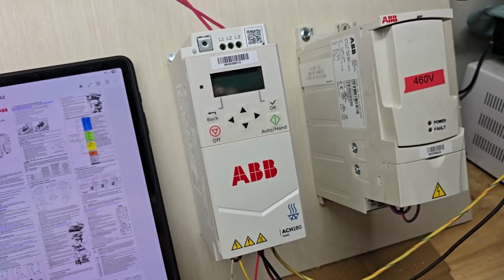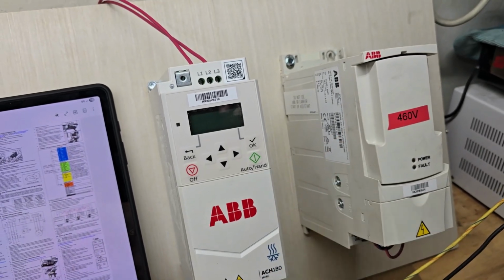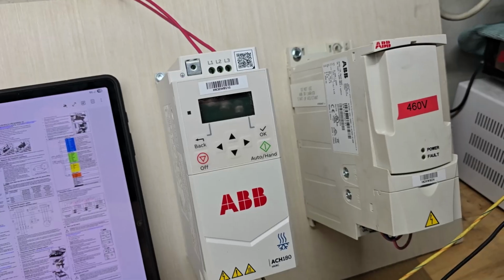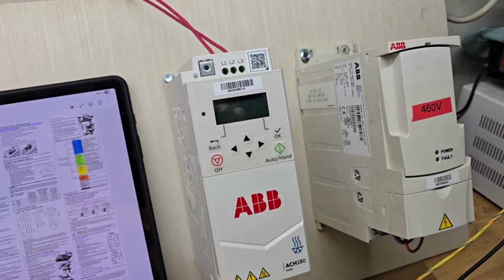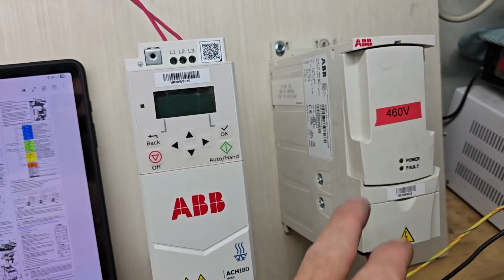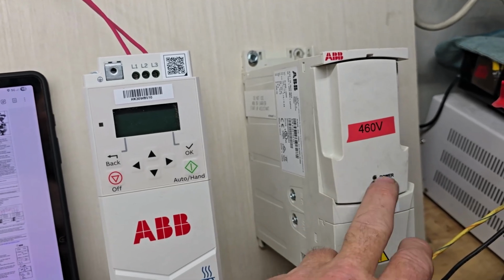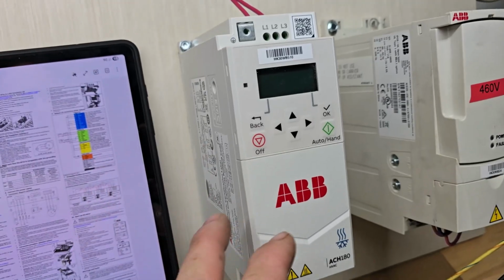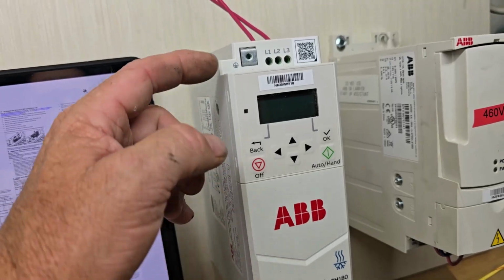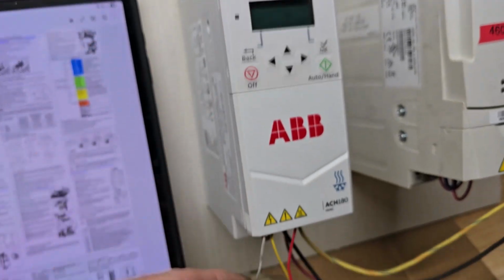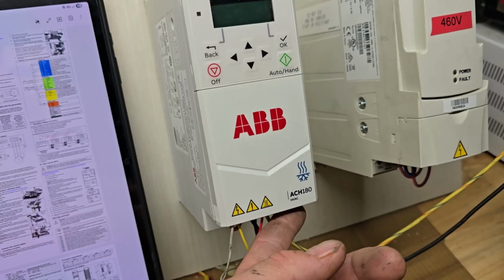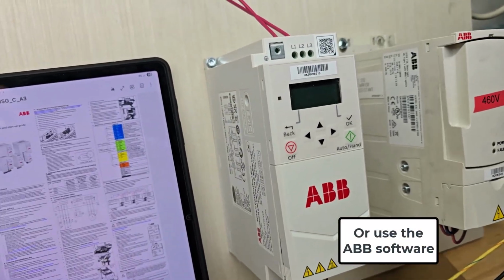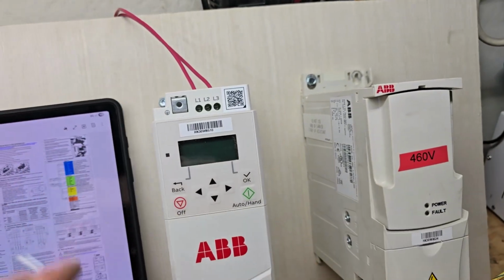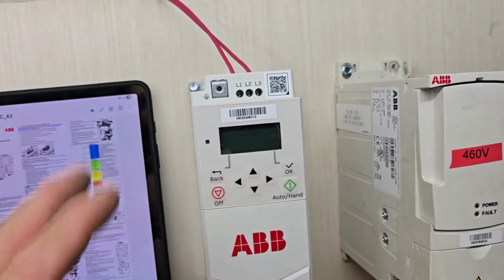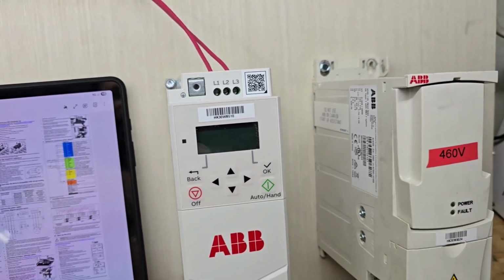Popular in Carrier units, they shipped with either an ABB ACS-320 or the larger ACH-550 drives. They usually didn't come with a keypad, just have this blank off cover, so you just have your power and your fault light. Replace it with the smaller ACH-180 that does not have a removable keypad. You can plug in a keypad through the bottom port, but that's about it. So they're going to come like this. It's pretty much a low cost, all built in one drive to replace this drive.